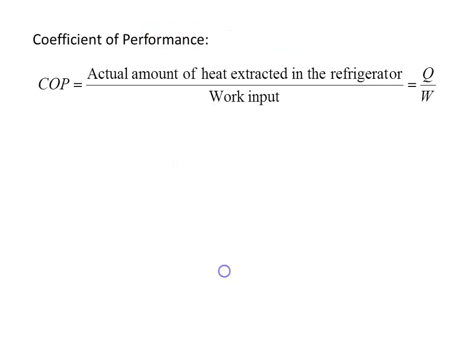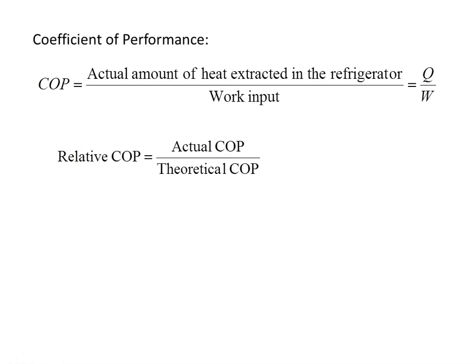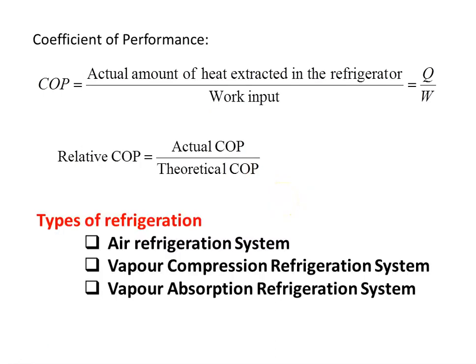Another terminology in refrigeration is coefficient of performance (COP). COP equals refrigeration effect divided by work input — the actual amount of heat extracted divided by work input: Q divided by W. There is also relative COP, which is actual COP divided by theoretical COP. The theoretical COP is calculated from the refrigeration cycle, and the actual COP is the COP of the actual refrigeration machine working practically.